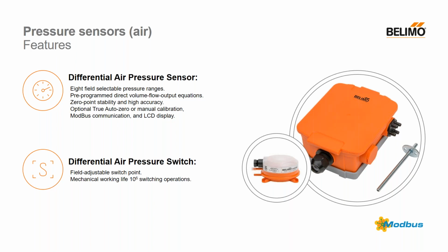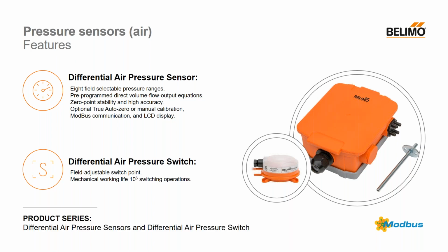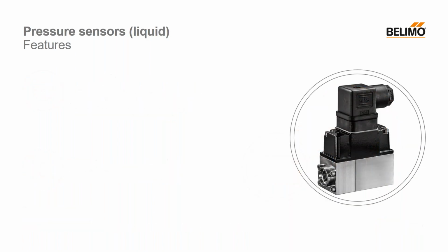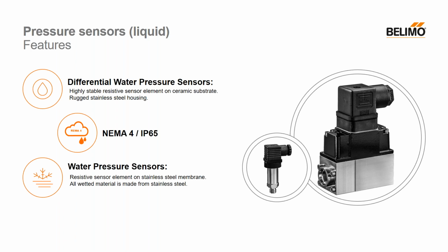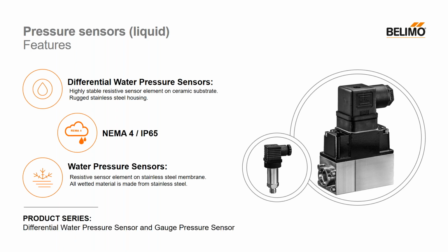We also have a standard differential air pressure switch, often used as a safety or things like that, just an air cutout. But again, a full product offering range of airside DP and airside differential pressure switch. So all the standard airside differential and absolute pressure offerings are available through Belimo. On the liquid side, we have both water side differential and water or refrigerant absolute or gauge pressure sensor offerings. On the differential pressure side, we have ranges that go from 0 to 15 psid all the way up to 0 to 100 psid in differential. The gauge pressure or absolute pressure ranges go from 0 to 15 psi to 0 to 200 psi.